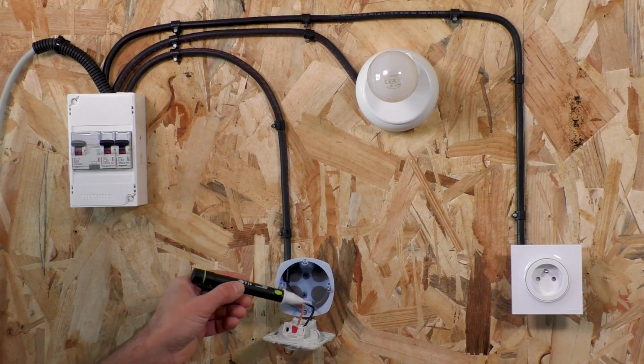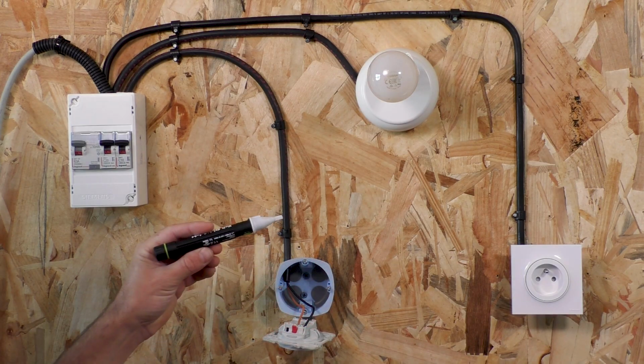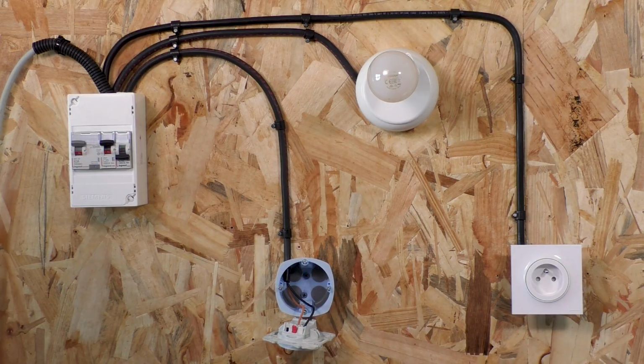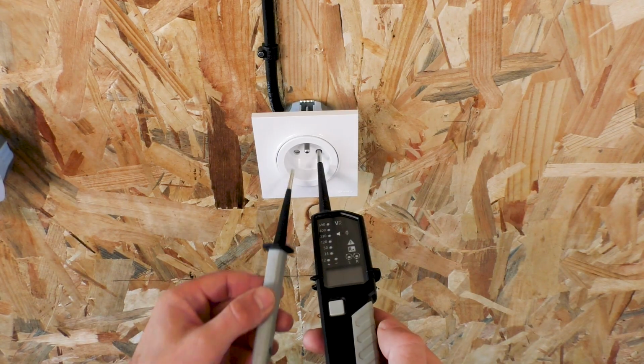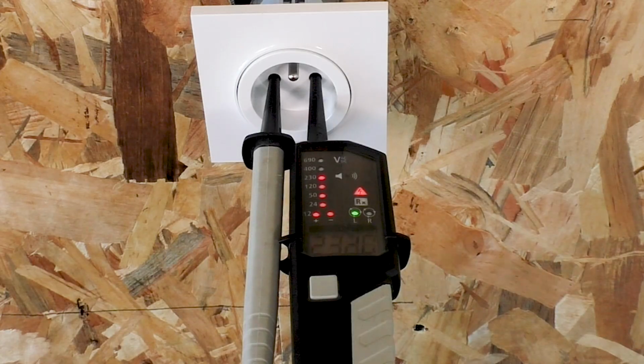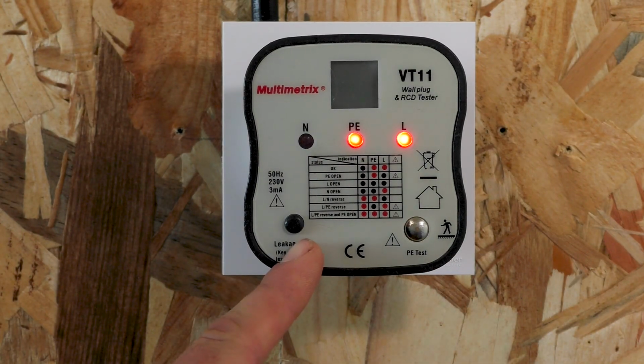So to recap, use a pen tester whenever you want to quickly check if something is live, energized, but take precaution. A voltage tester, whenever you have a neutral wire, it's more reliable. And when you actually want to test for voltage and not just to see if something is energized or not. And a socket tester to quickly confirm wiring and grounding of your sockets. All three are simple, inexpensive, and make your DIY work a lot safer.